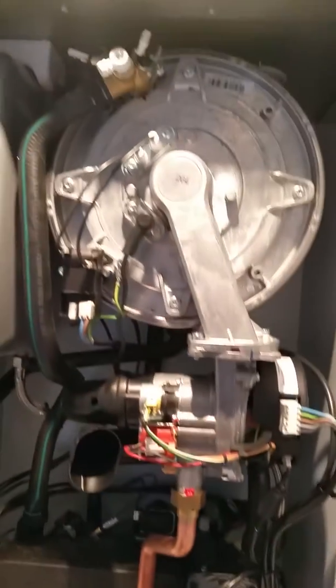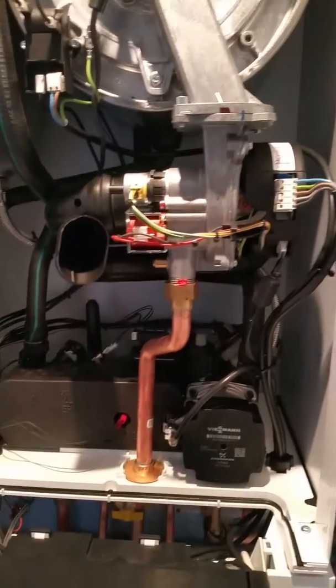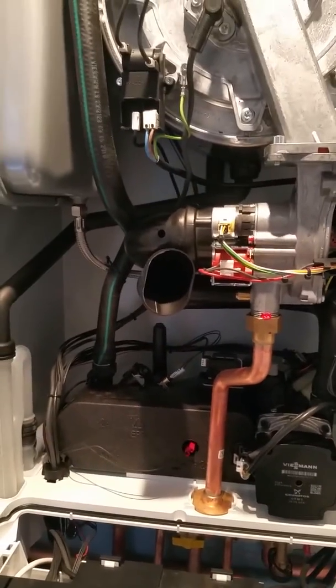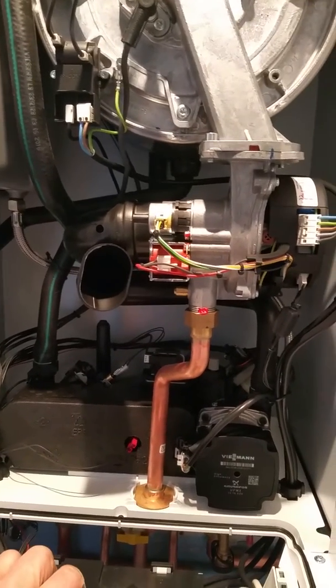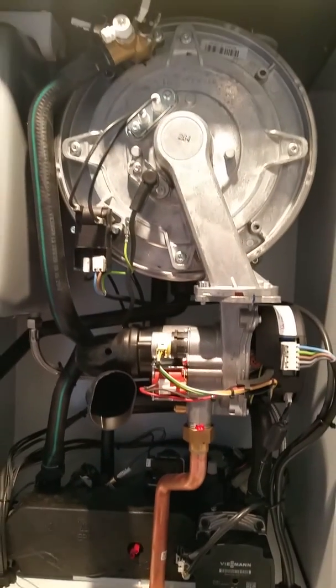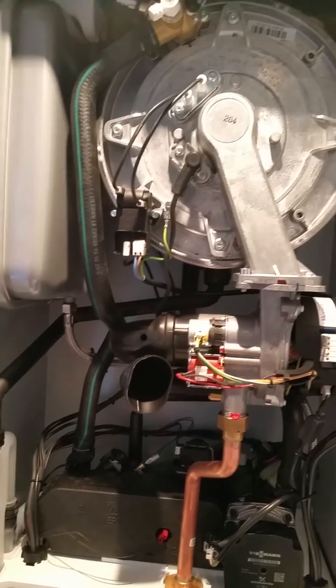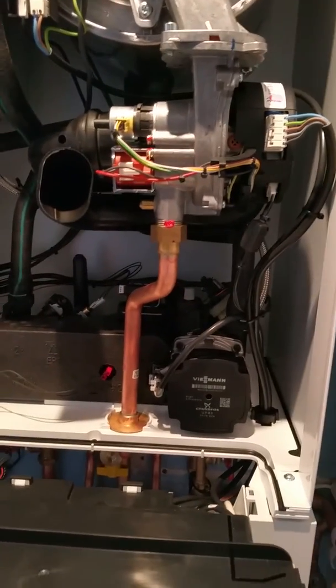So just about any other boiler other than this as a combi would have been cycling like crazy, but now I can give maximum size 35 kilowatts and expect to see almost no cycling from the boiler. As usual, I've cabled it in for weather compensation, it's over in the back there. So, very easy install.